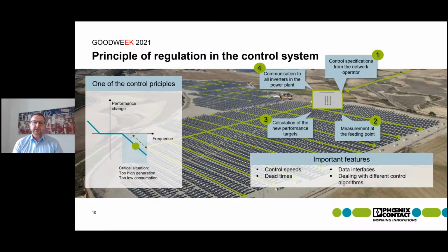That is a very important feature, so that you have really good supporting power output from your solar plant to the grid. In addition, you have to handle different data interfaces from the network operator, because we can receive the data via digital signals, analog signals, or, what is coming more and more in Germany, via serial interfaces. You also have to communicate with the different inverters, and therefore you need different inverter communication protocols. And you have to deal with different control algorithms. It's not possible to have only one algorithm to control, for instance, the active power according to frequency. That is one characteristic, but at the end, if you follow the European grid codes, it's necessary to have more algorithms inside your control system.